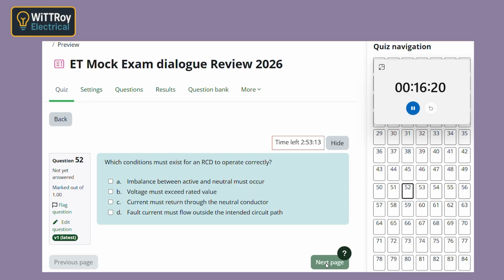Correct. For tripping to occur, some current must leave the intended path and not return through the neutral conductor in the normal way. That is why the option about fault current flowing outside the intended circuit path is also correct. So why is voltage must exceed rated wrong? Because RCD operation is not based on supply voltage exceeding some threshold, it is based on current imbalance. People often confuse voltage problems and protection problems, but this one is about imbalance current.